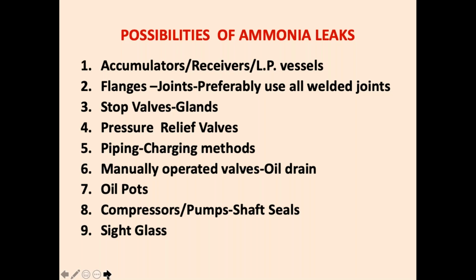Now, which are the areas where ammonia could leak? It could be vessels, accumulators, receivers, LP vessels. Major are flange joints, so try to avoid flange joints preferably. Use all welded joints. Then stop valve glands. If you don't lubricate the stop valve glands and they become dry, there could be a leakage of ammonia from the glands of the stop valves. Pressure relief valves, if they are leaking, there could be ammonia leaks. During refrigerant charging, using the wrong pipe or an incorrect method of charging can lead to big ammonia leakages.